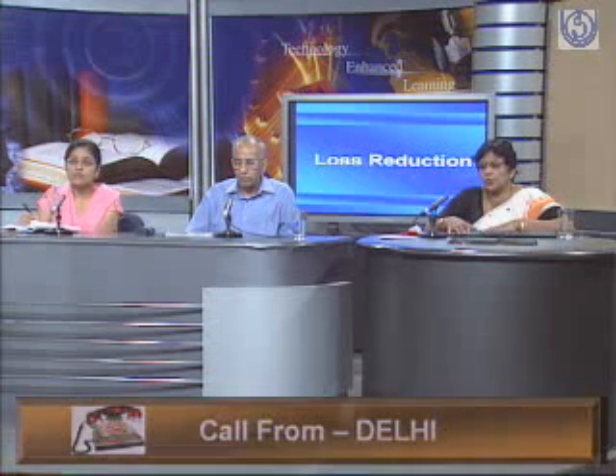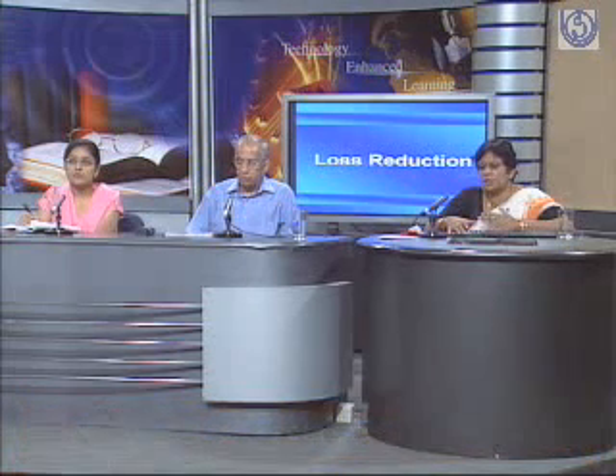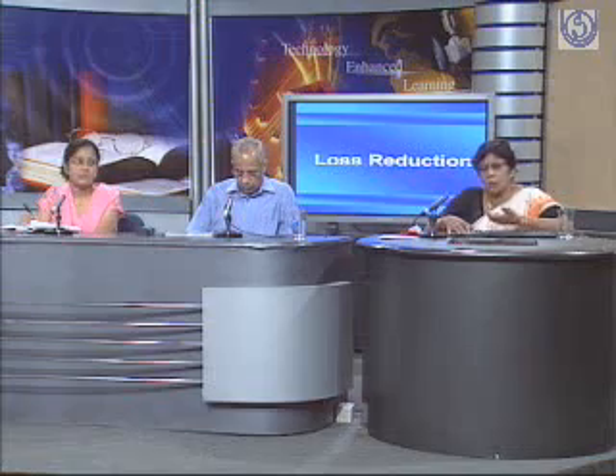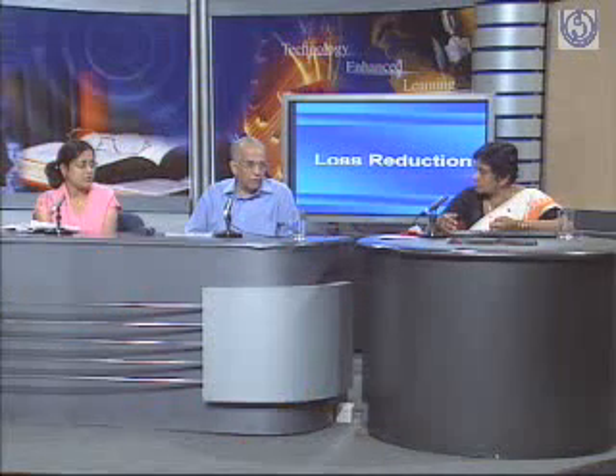It is not possible to have a reverse reading in electronic meters while you are downloading. The downloading instrument, which is the MRI or the CMRI, the common meter reading instrument, is plugged into the optical port of the electronic meter, and the data comes just like what comes in a floppy or a CD. So it will come as it is from the meter. But whether the question pertains to electronic meters recording a reverse reading so that the bill can be reduced: no, it will not record a reverse reading normally.